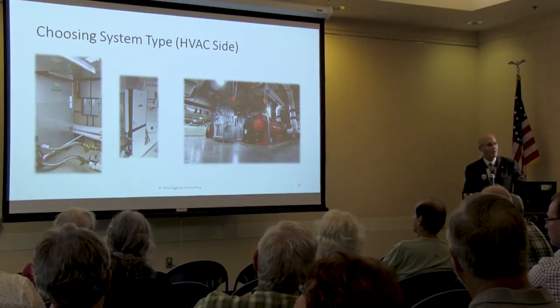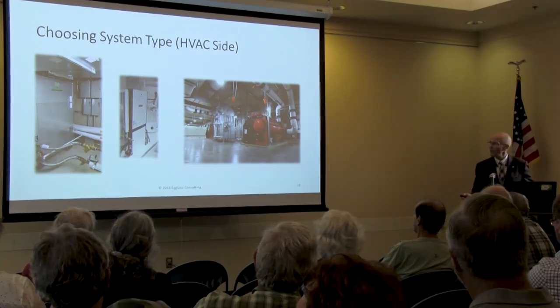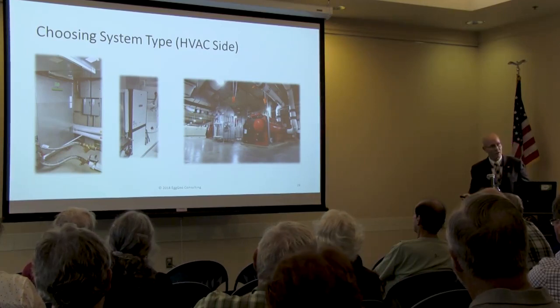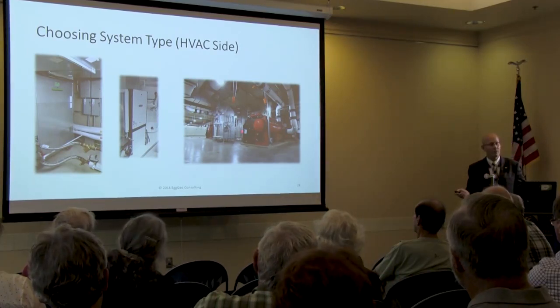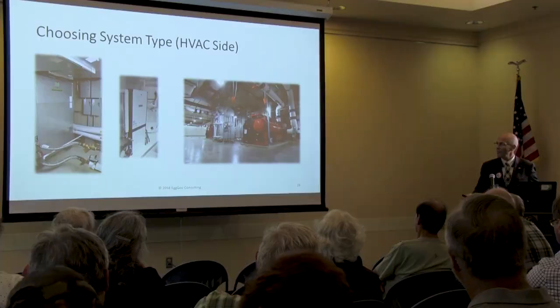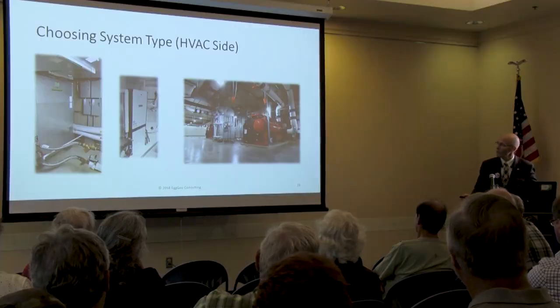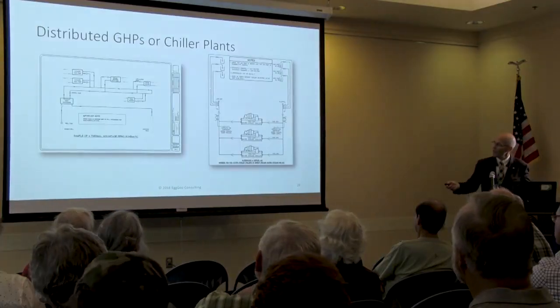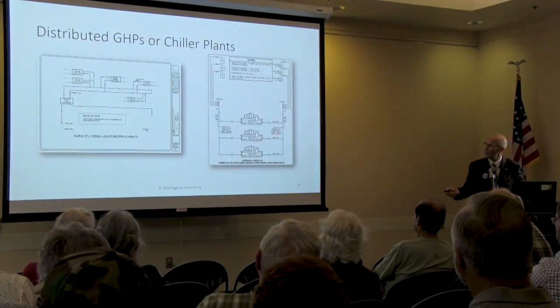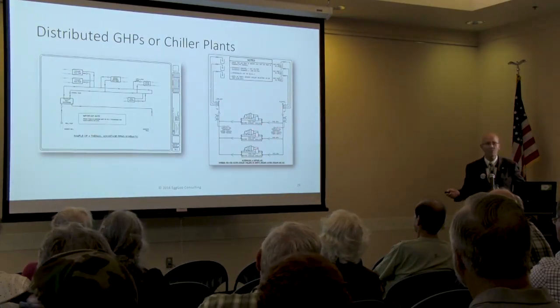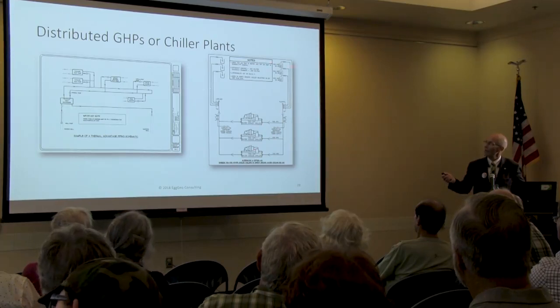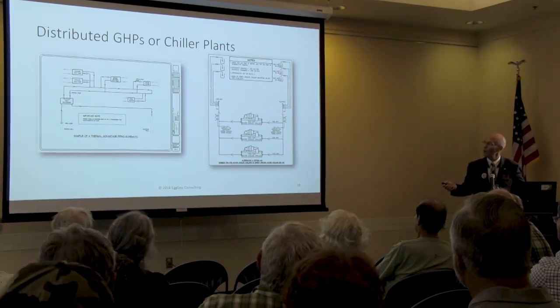Now when you get into a college campus or a downtown building, you have what's called a chiller energy plant. This is a chiller, a centrifugal chiller. That can be geothermal source too. As a matter of fact, many, many are. And this is when I talked about the economy of volume. These bad boys really, really work well on geothermal sourced systems. So this is kind of what it looks like in an engineering diagram. Here are three 700-ton centrifugal chillers, and they're being sourced by geothermal wells.